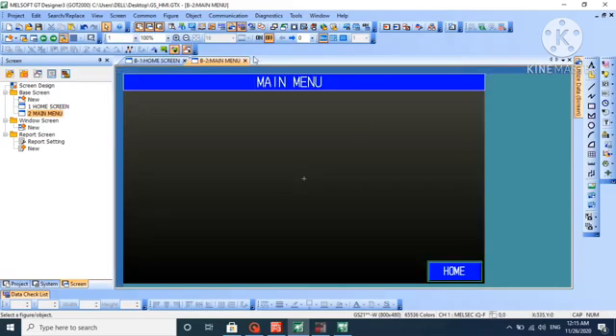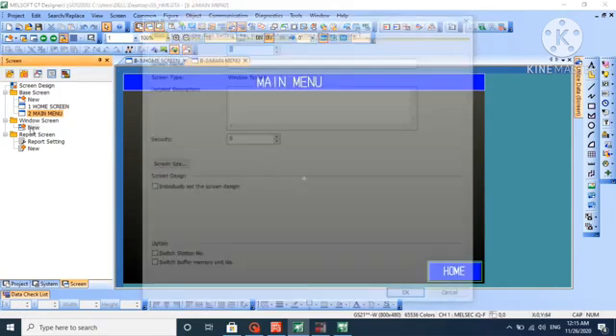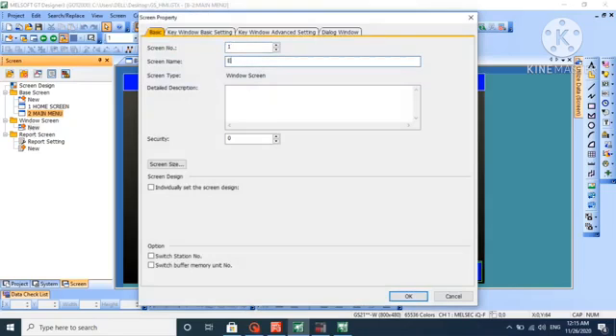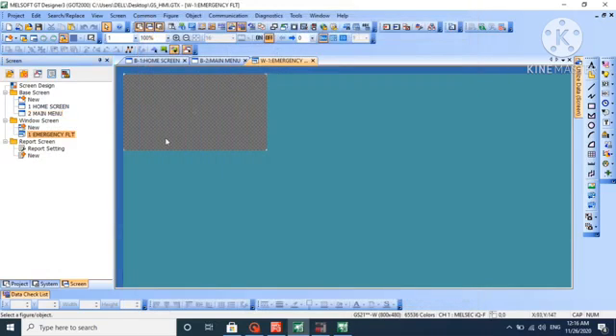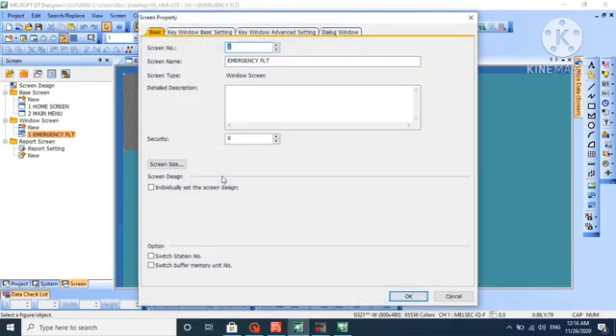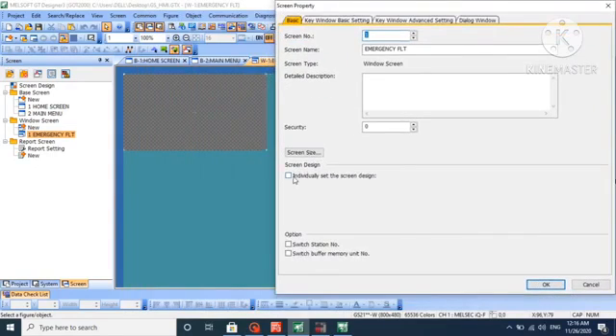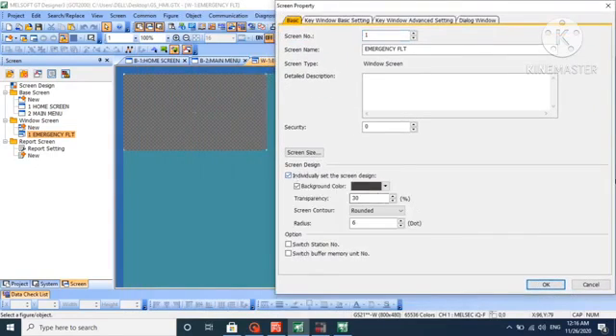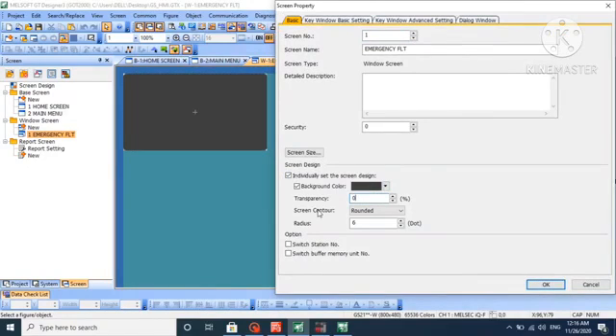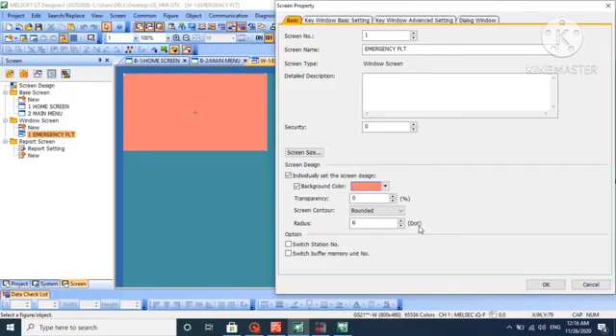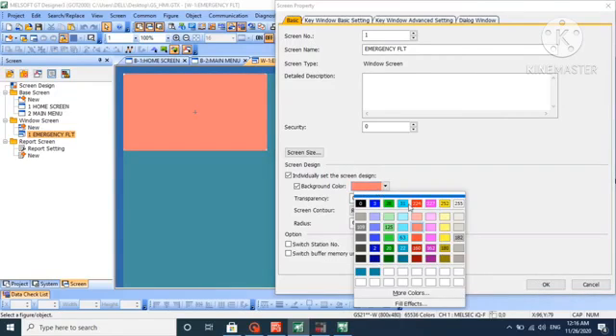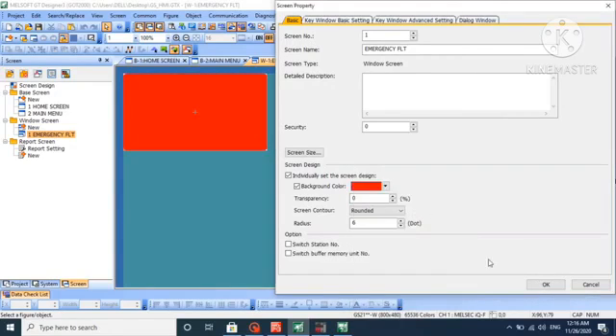Now we will create some window screens. Generally, window screens are used for some kind of alert pop-up, like fault or emergency conditions. We'll create an emergency fault window. The window screen default size is smaller compared to base screen. We can adjust the color in properties. We're putting transparency to zero and changing the color to red.